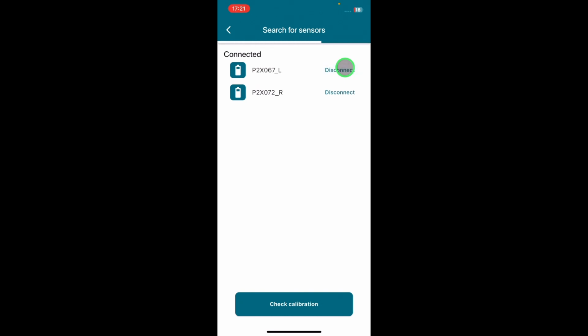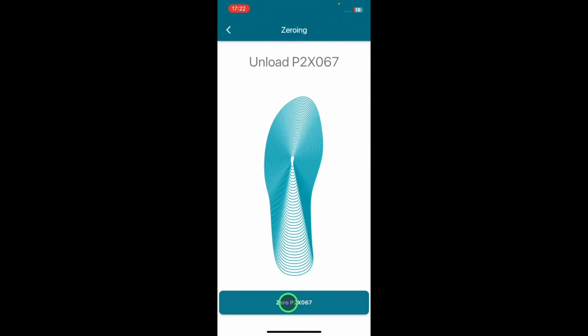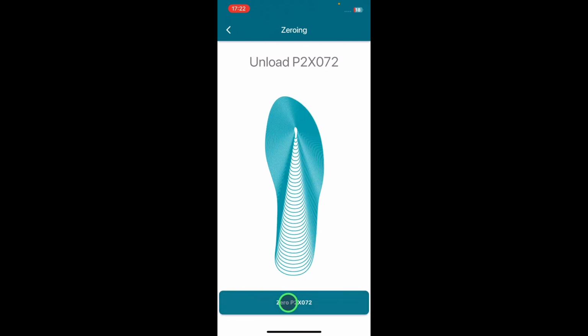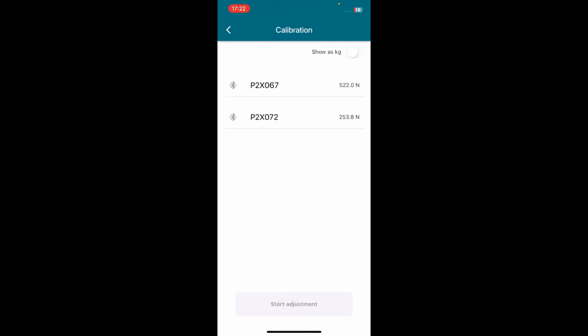Now it's highly recommended to check the calibration. For loadsols, that could be done with body weight, while for load pads, some dead weights could be used. Go and check calibration, unload the left insole, unload the right insole and confirm. And now we can see on each side here the forces.